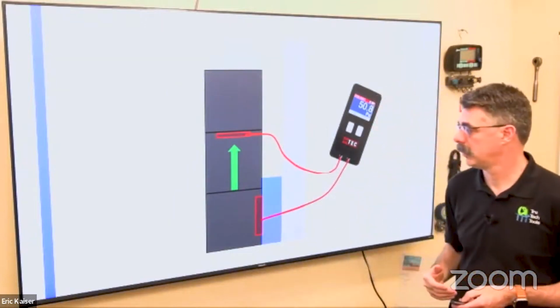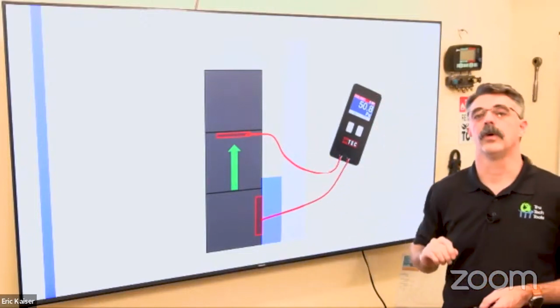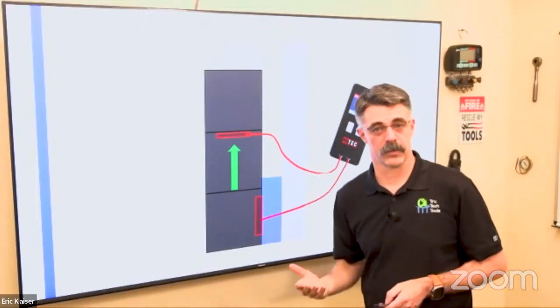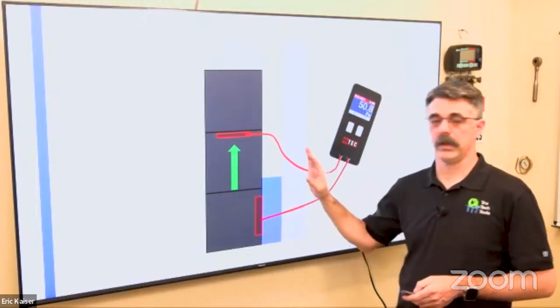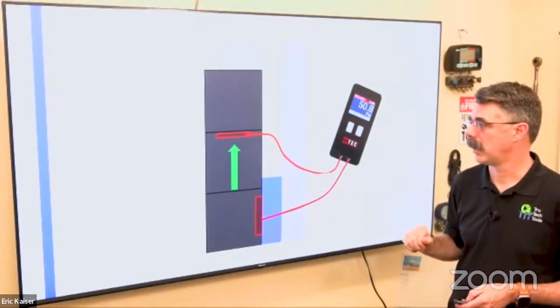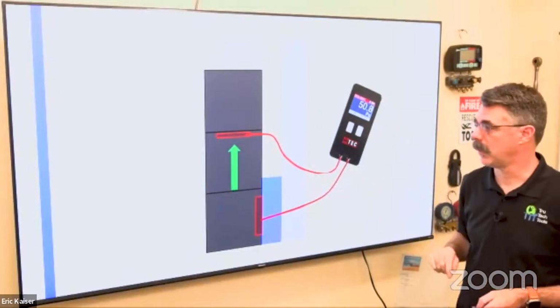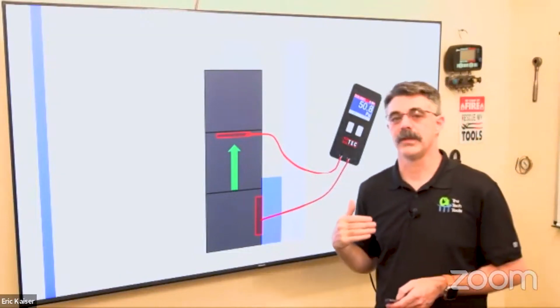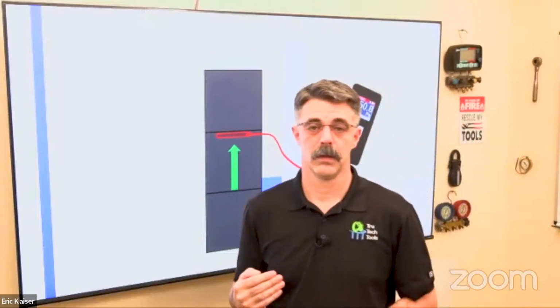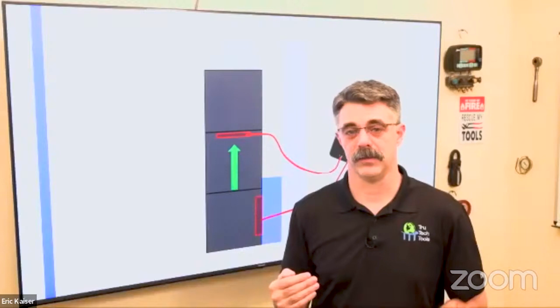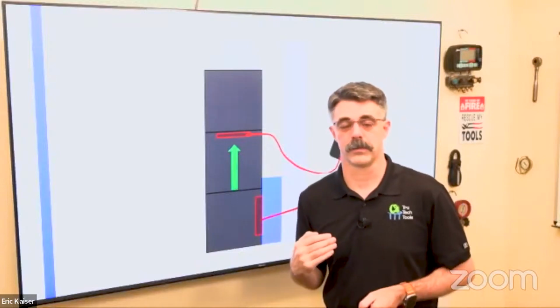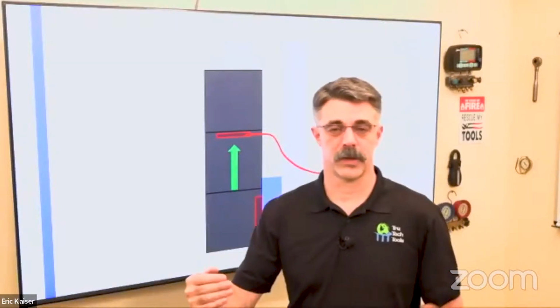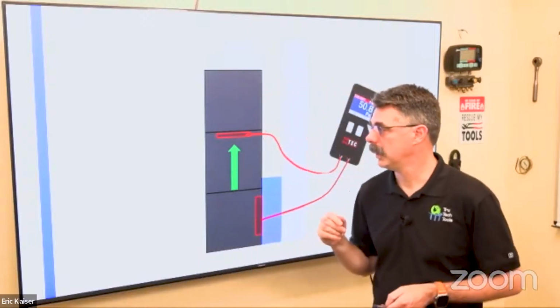Now, one of the first things we need to do, if the old equipment is still operating well enough, if we can still move air through it, the blower's still good, we really need to take a static pressure reading. All right. Take your static pressure reading. I'll show you why here in a little bit, because that's going to help you predict what the new equipment is going to work like, especially if you're changing sizes. A lot of times what contractors are finding is that gas furnaces are way oversized and we can get away with a lot smaller unit, which is great for a heat pump. We'll talk about that in a little bit too.